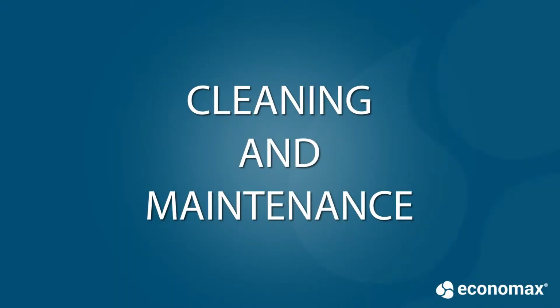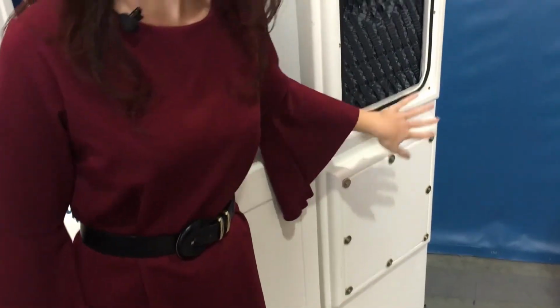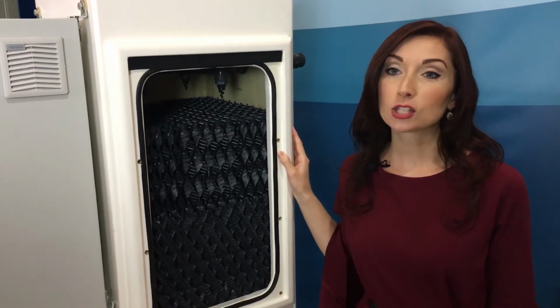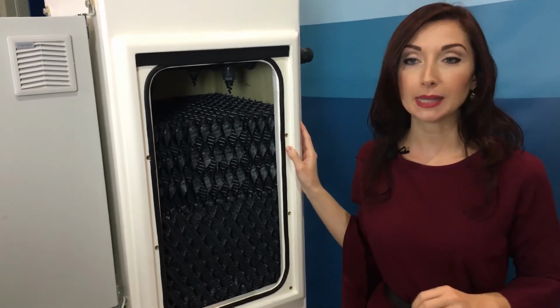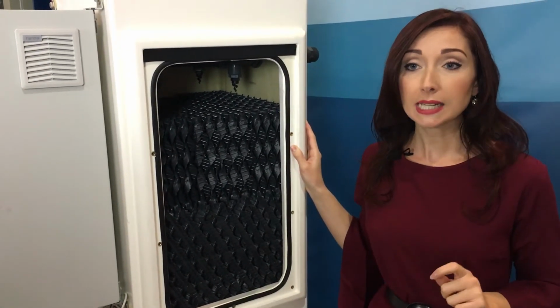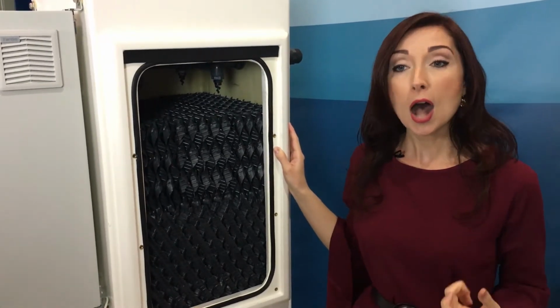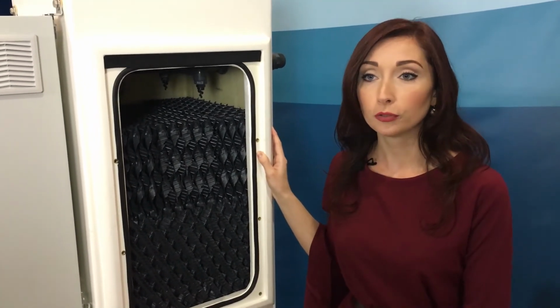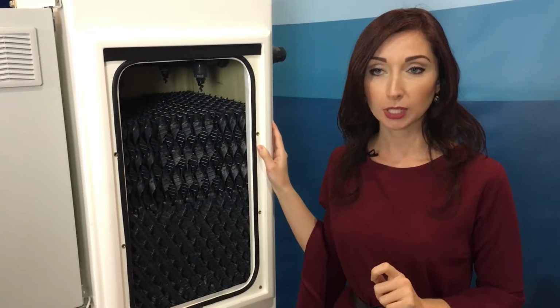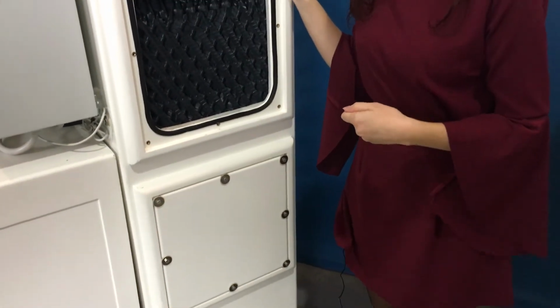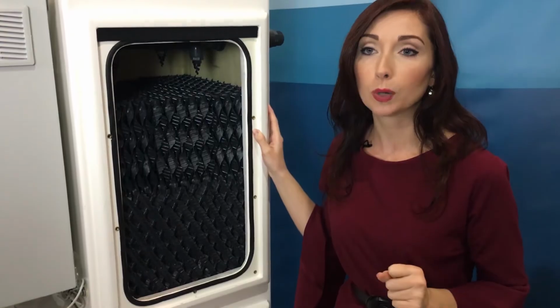Cleaning and maintenance. Tower maintenance is an extremely easy but essential operation. All the internal components are easy to access for carrying out inspection, maintenance, and cleaning, thanks to the 2 large hatches placed on the sides, one with access to the tank and the other to the honeycomb heat exchanger. You can easily extract and substitute the filling materials by buying replacements. You should substitute it about once a year depending on the condition of the material. Always ensure that no channels are blocked by limestone deposits or dirt, so that water can always flow freely to be cooled as efficiently as possible. To clean the tank, you can simply empty the tower from the Output tab on the back and remove the lower panel.